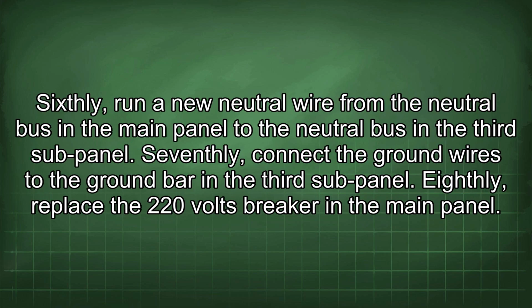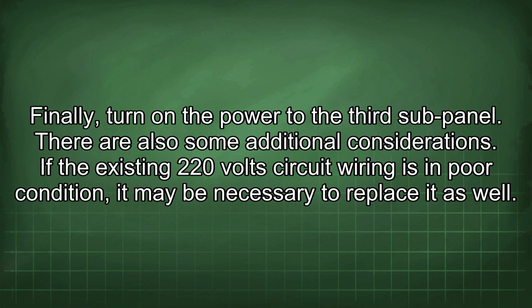Sixthly, run a new neutral wire from the neutral bus in the main panel to the neutral bus in the third subpanel. Seventhly, connect the ground wires to the ground bar in the third subpanel. Eighthly, replace the 220 volt breaker in the main panel. Finally, turn on the power to the third subpanel. There are also some additional considerations. If the existing 220 volt circuit wiring is in poor condition, it may be necessary to replace it as well.